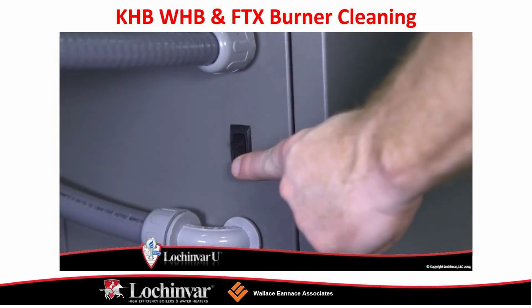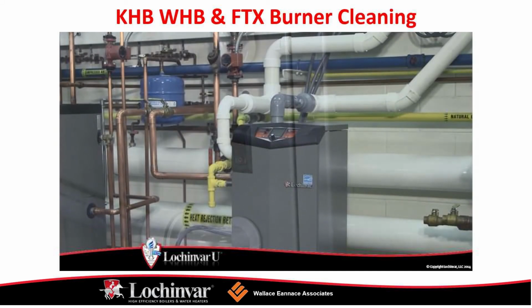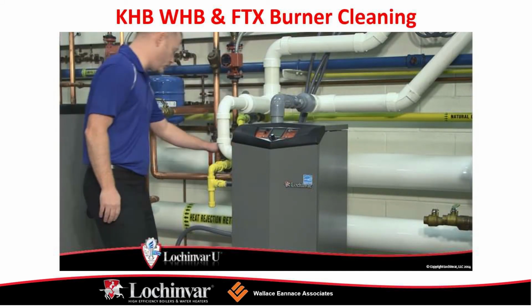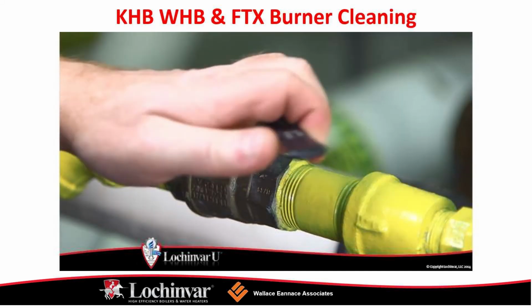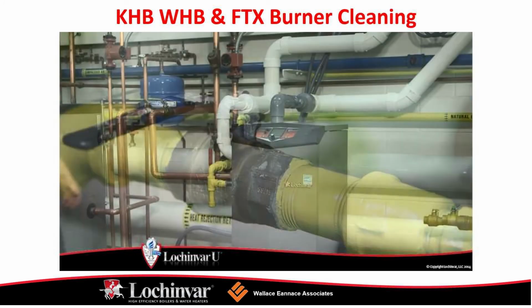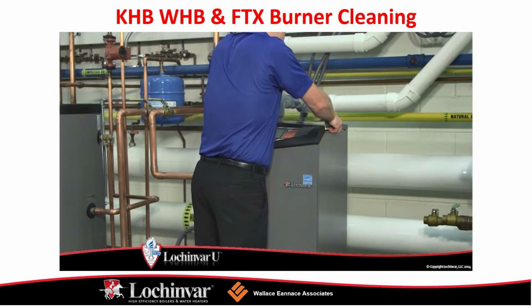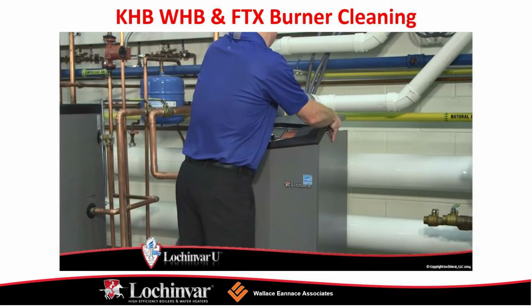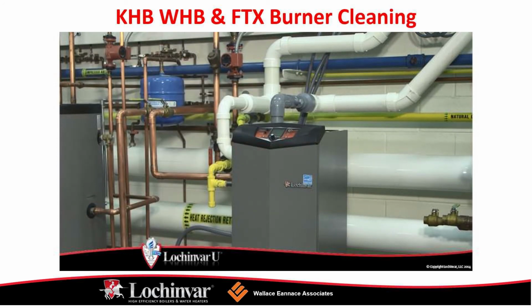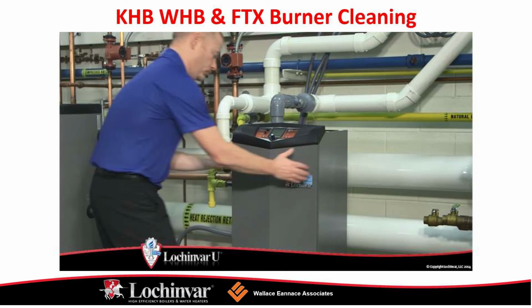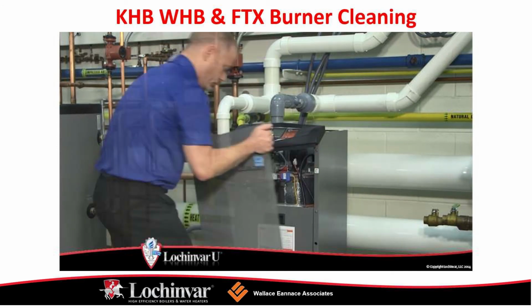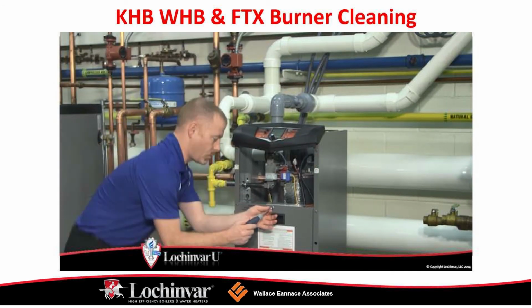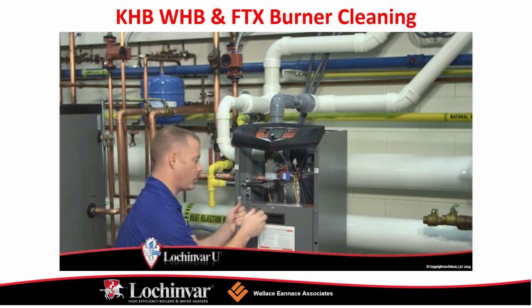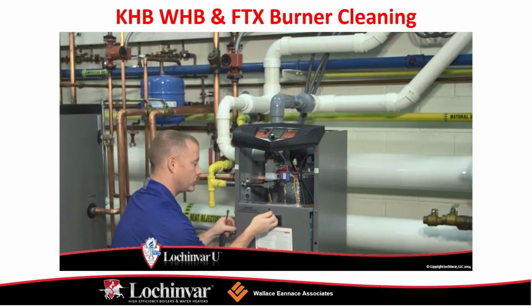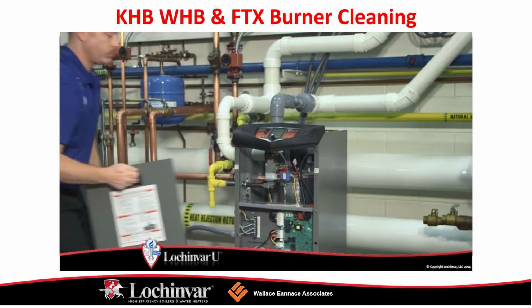After one adjustment to the valve, take time to allow the combustion to stabilize and recheck the combustion levels. If the combustion levels are still not within the specified range, repeat the adjustment procedure. If after 4 adjustments the combustion levels are still not within the specified range, revisit the other possible causes or replace the gas valve. Once the combustion analysis is complete, press the right select key to take the unit out of service mode. The unit will return to normal operation.